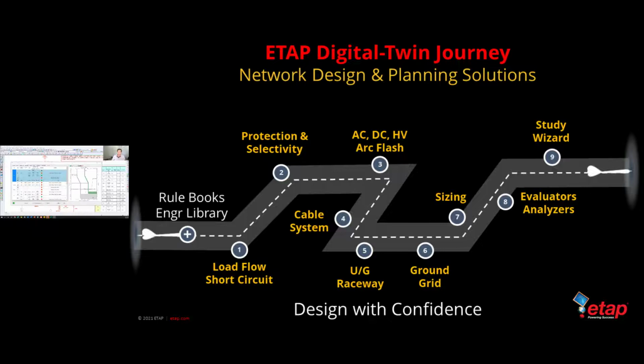But the beauty of it is, if I make a selection or a change, as soon as I change it, I can go back to the coordination. So if I go to substation 3 here and look at the bus side, if I make a change, as we saw before, and want to go below substation 3's bus side limit, I can make that change and realize it passed arc flash.